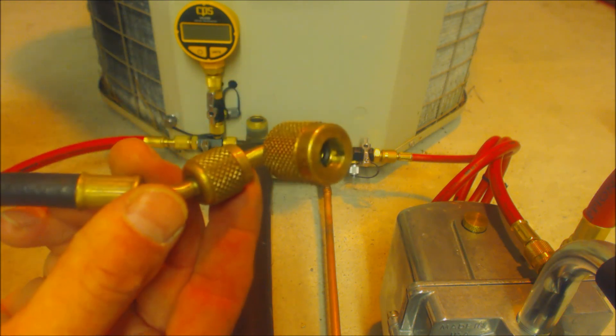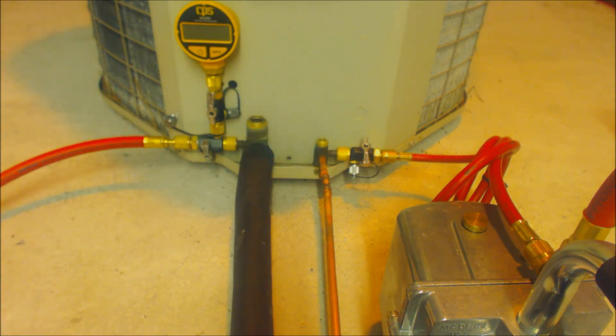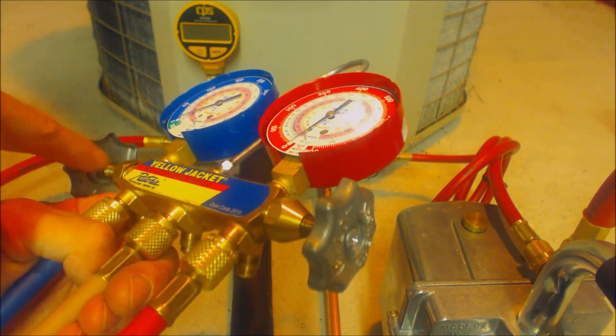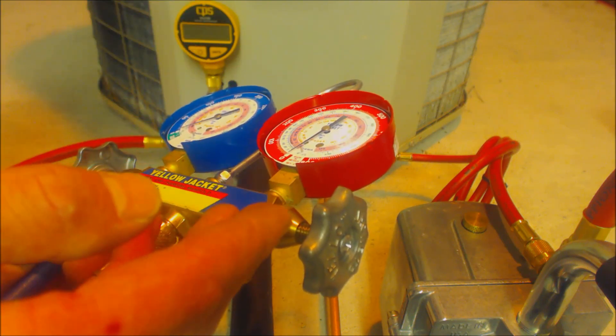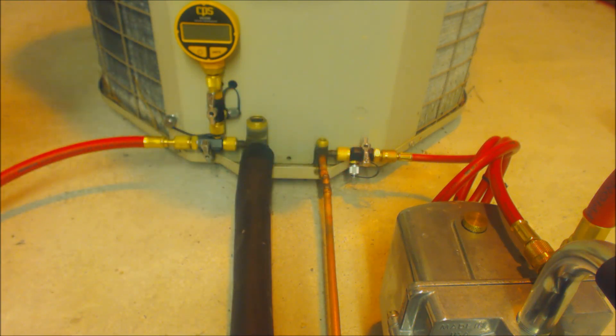Maybe you're trying to pull a vacuum through a quick disconnect fitting or something like that, and that's leaking. It's possible to end up having the handle here leaking on your manifold gauge set if you're pulling a vacuum through this. If you've put this through a whole lot of use over years, then you might have to rebuild that handle assembly.